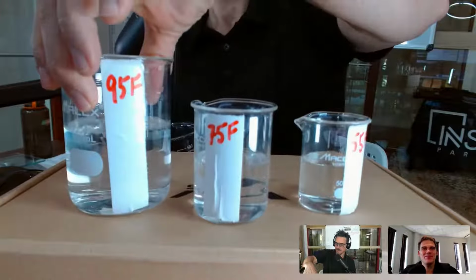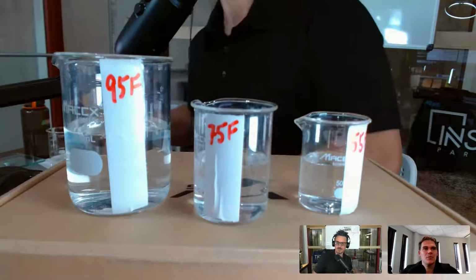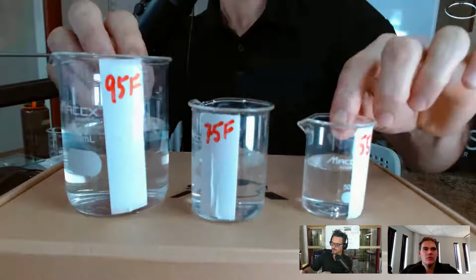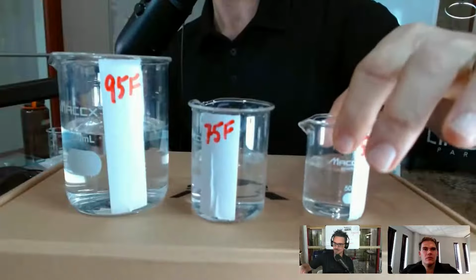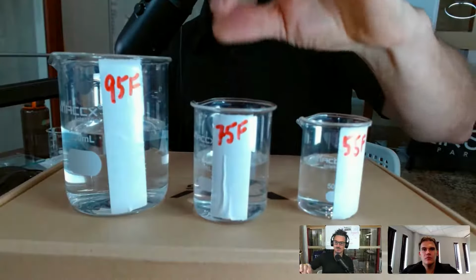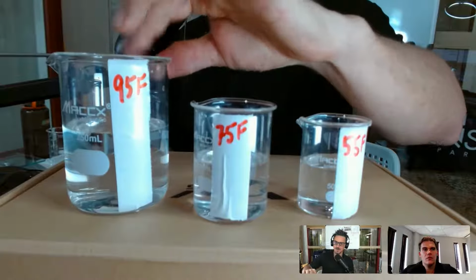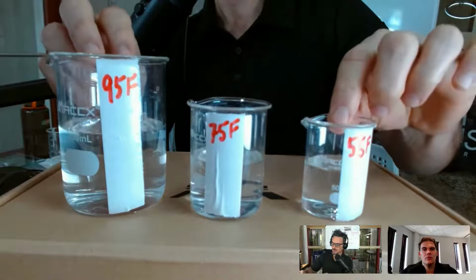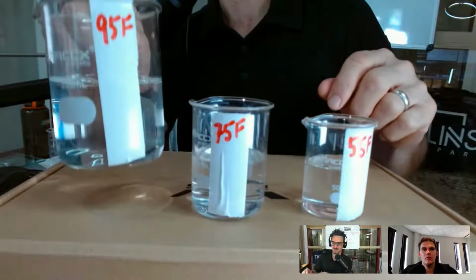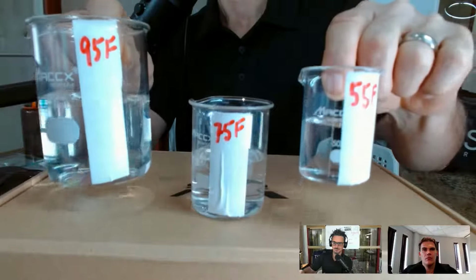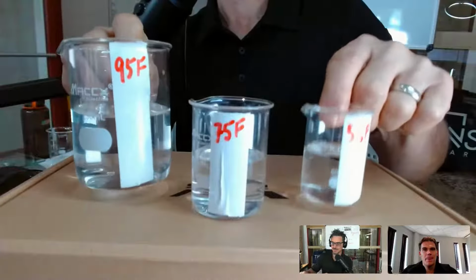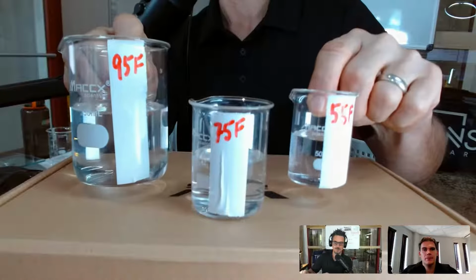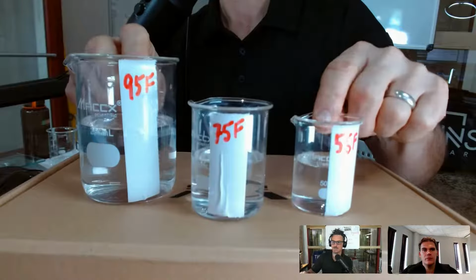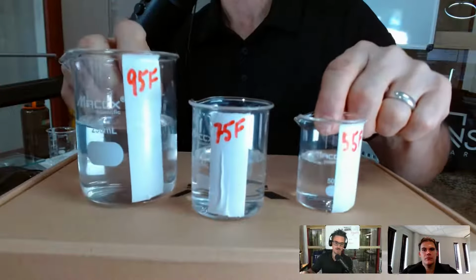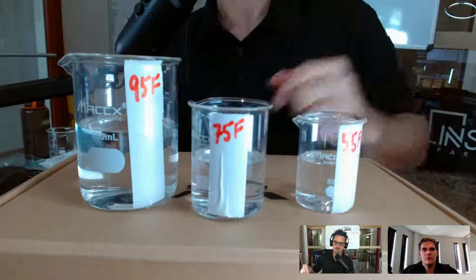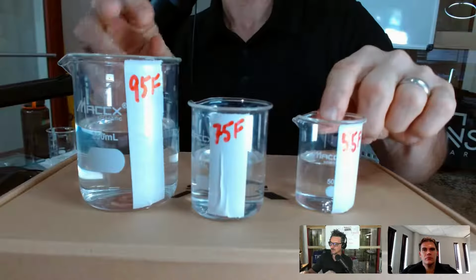Okay. So you would expect these beakers to look something like this if these were 50% full. So air versus how much it can hold: 50% RH at 55 degrees, 50% RH at 75 degrees, and 50% RH at 95 degrees. Now, here's the important lesson. What do you notice about the volume of water in this beaker versus this beaker? Well, the volume of water is much greater here, but they both have the same reading of 50% relative humidity. Therein lies the issue when using RH to determine the actual amount of moisture in the air, because it is relative to the temperature that the air is at. So the higher the temperature, the more water it can hold.